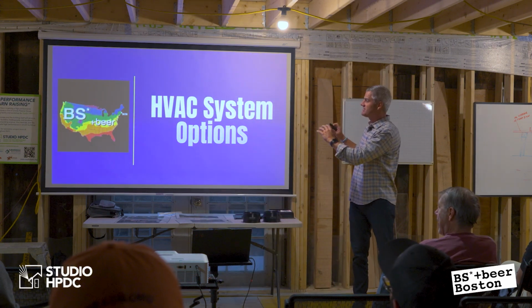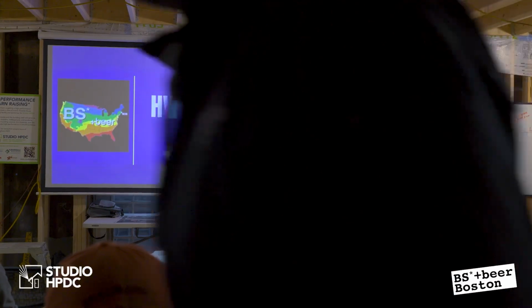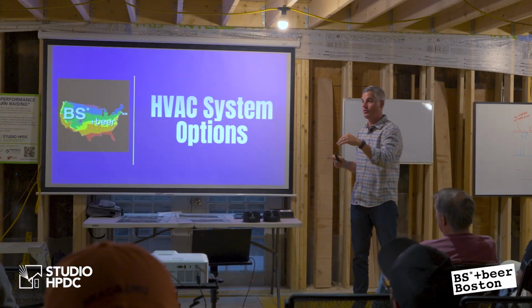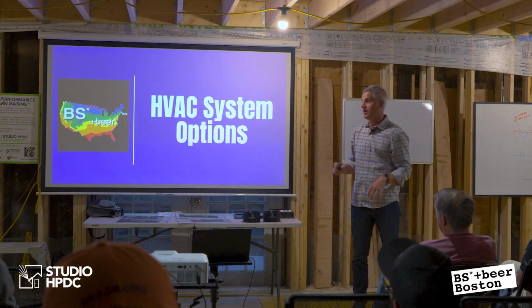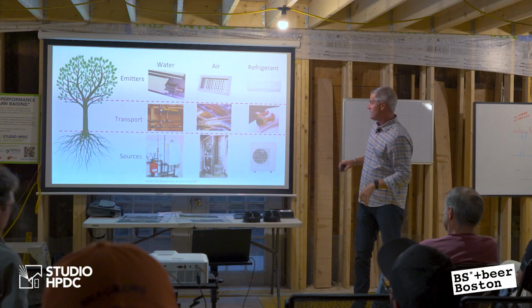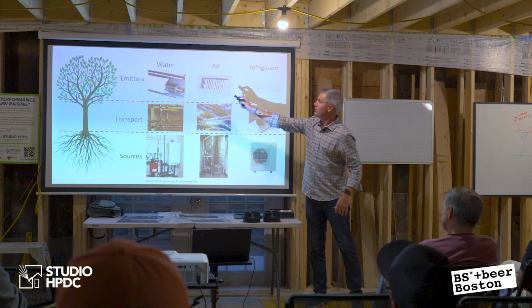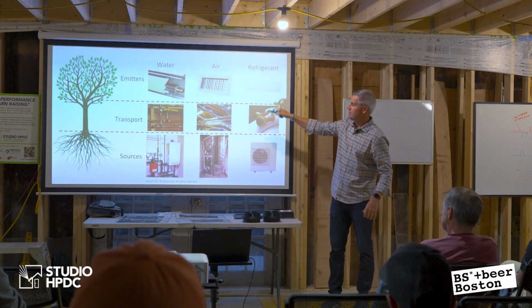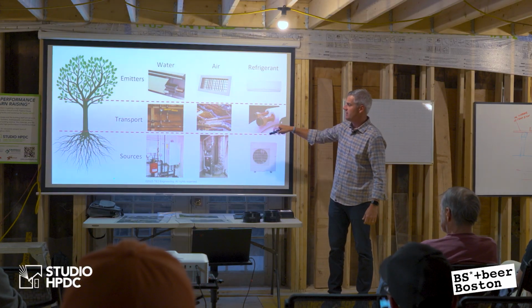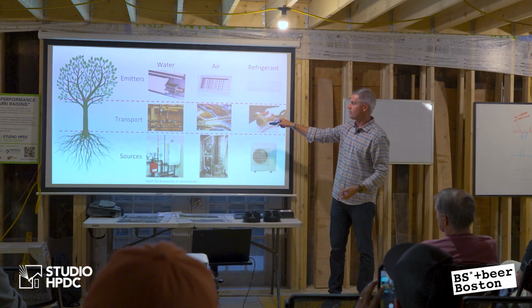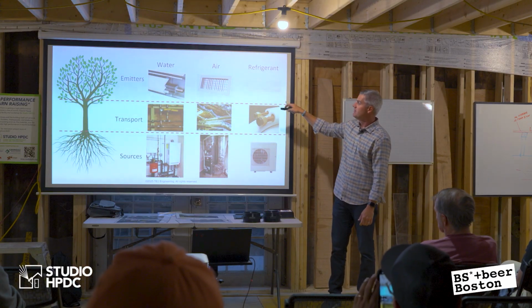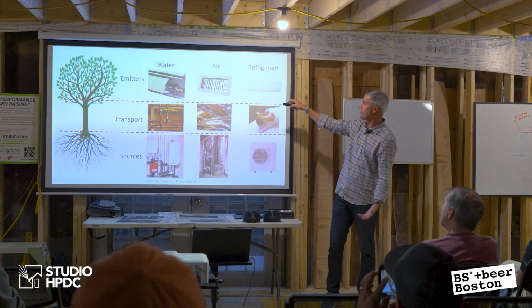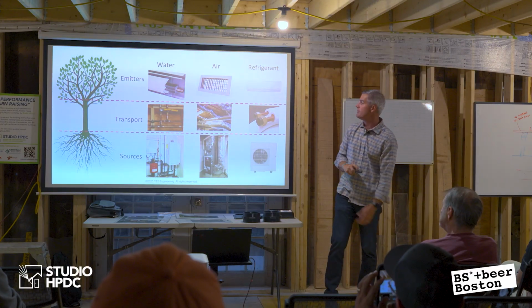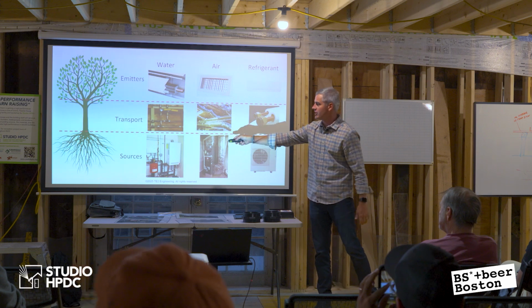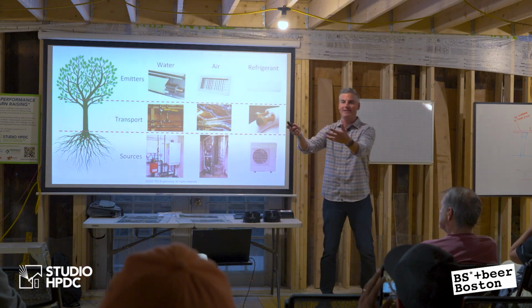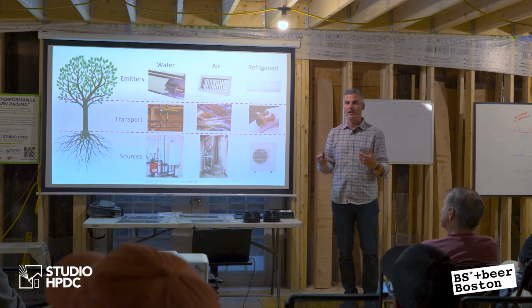All right, so we got two parts to this next bit. First one is HVAC system options, just kind of high level, what are the options out there? And the second part is about the barn specifically, doing a deeper dive in the barn. So just real high level, right? You can move heat with water, air, or refrigerant. You have sources that generate the energy. You can transport it through piping, through ductwork, or through refrigerant piping, and then you have emitters, like a register or mini splits or fin tube. I think of it as a tree. I've got to generate the energy, transport it, and then emit it. So that's the way I think about every HVAC system.